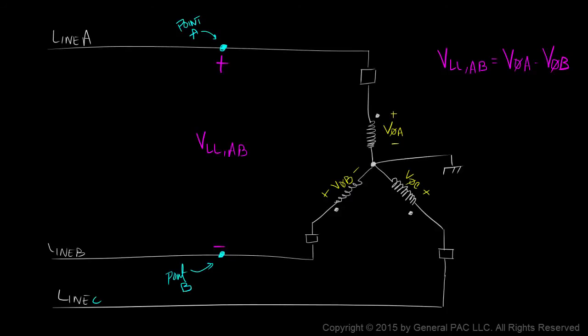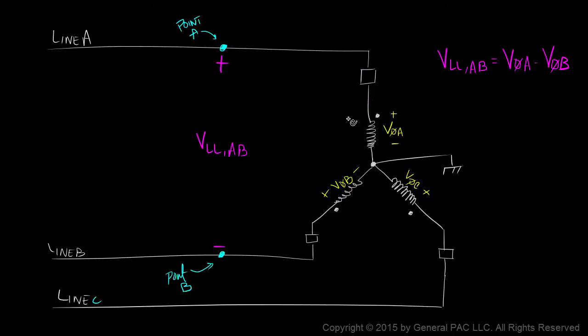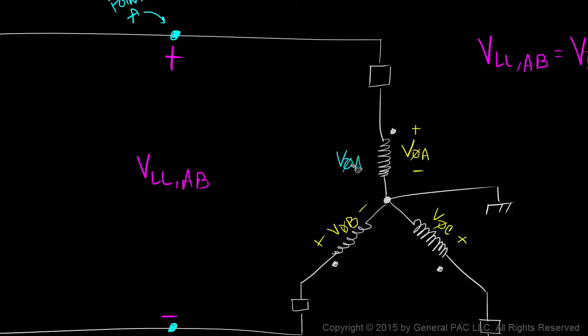Let's look closely at this equation from a different perspective. We'll label the points of measurement for the line-to-line voltage as point A and point B. Relatively speaking, we can expect the voltage on point A and the voltage on the bushing of winding A to be the same. So what about the voltage on the polarity side of winding A? It's pretty much the same voltage since it's the same point on the line. Now, if we measure the voltage from the polarity side of winding A to the non-polarity side of winding A, we'll get phase A voltage.